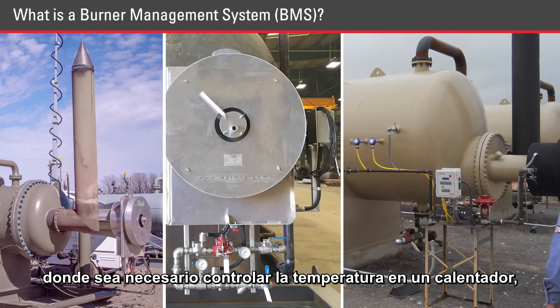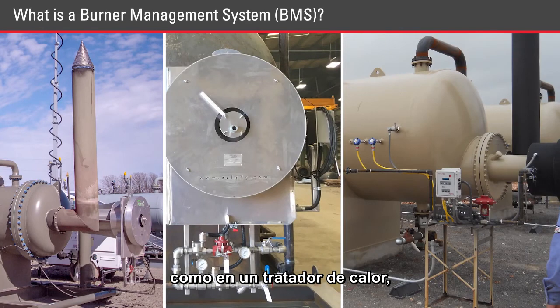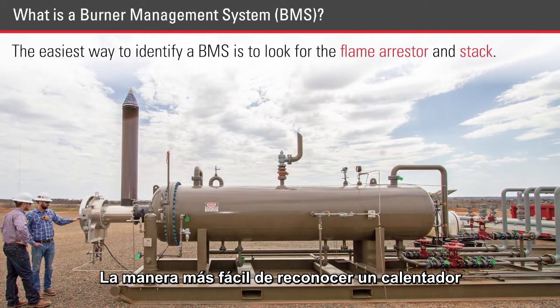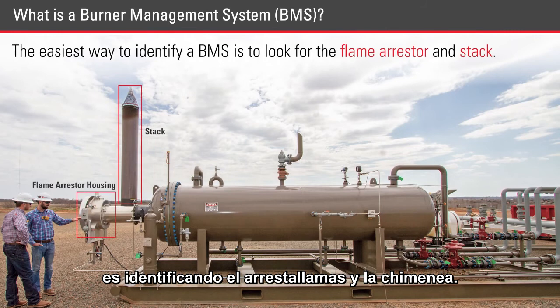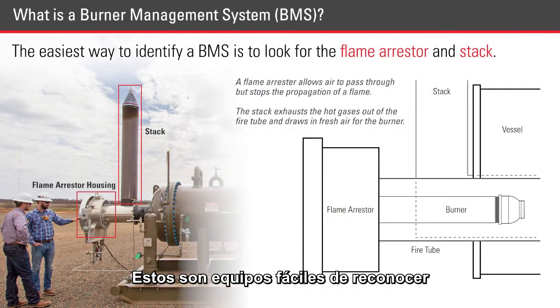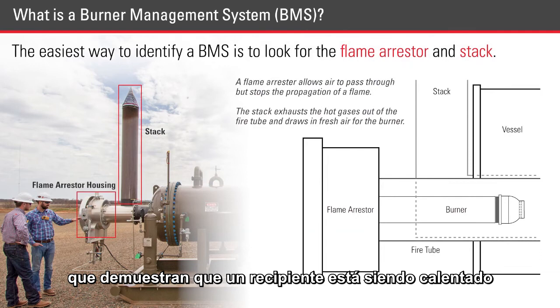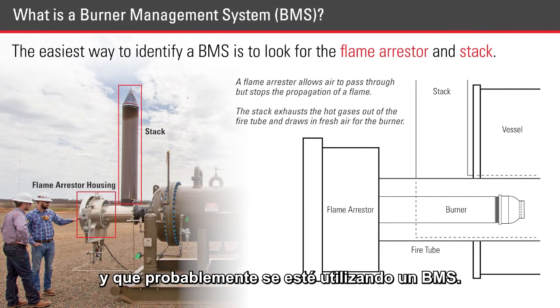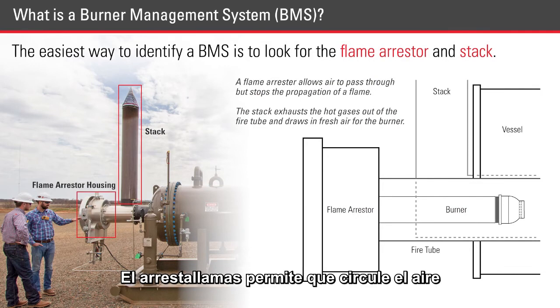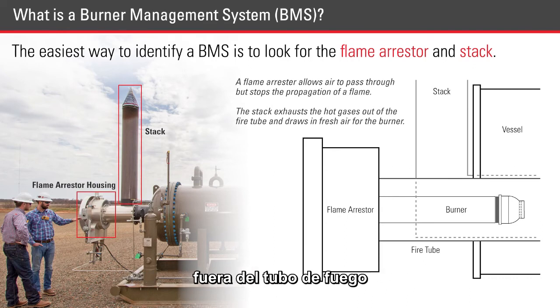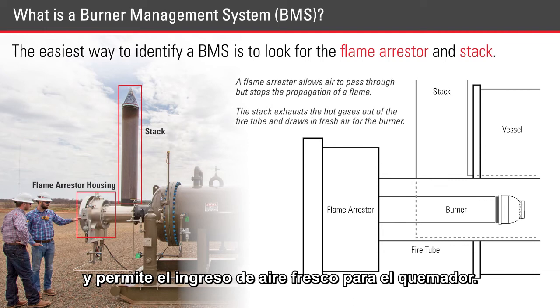You'll find a BMS anywhere that heat is being controlled within a vessel, such as a heater treater, line heaters, and some horizontal separators. The easiest way to identify a heated vessel is to look for the flame arrestor and stack. These are easily recognized pieces of equipment that signify when a vessel is heated and a BMS could be in use. A flame arrestor allows air to pass through but stops the propagation of a flame. The stack exhausts the hot gases out of the fire tube and draws in fresh air for the burner.